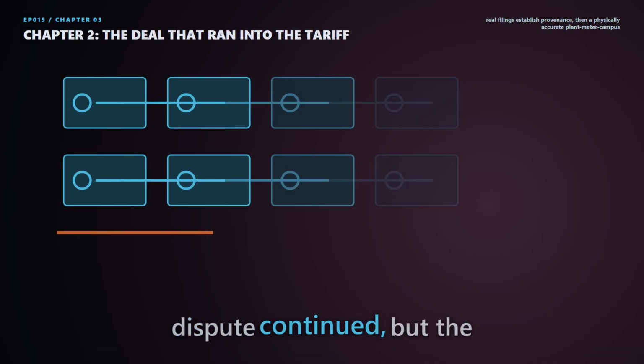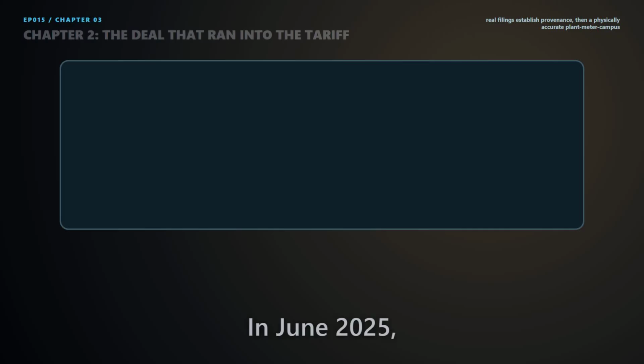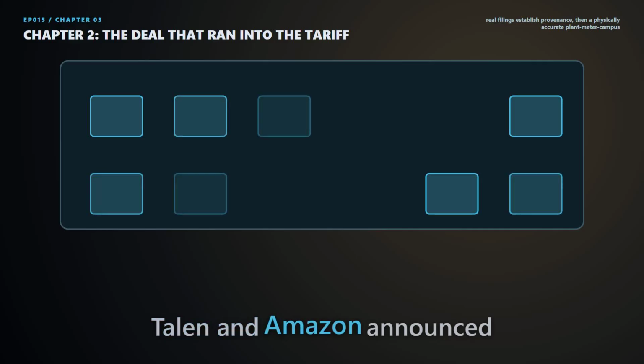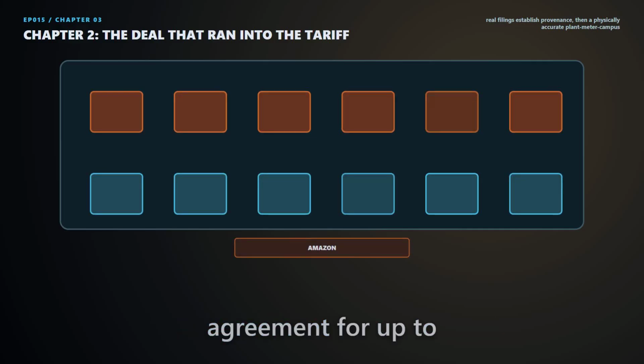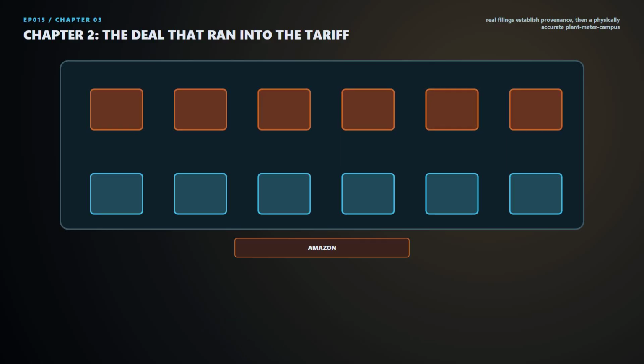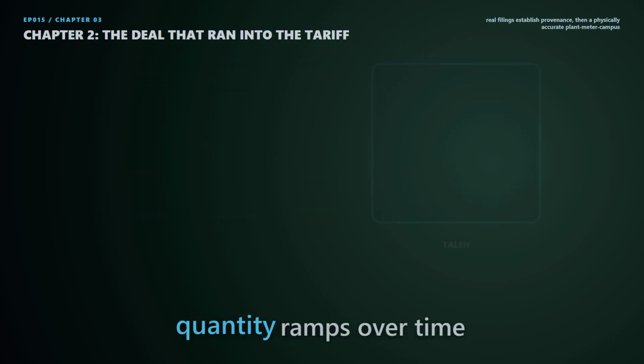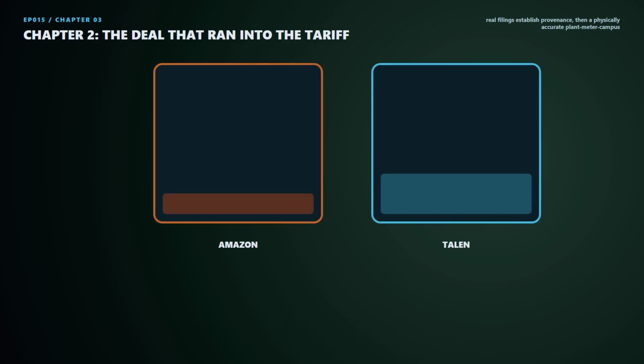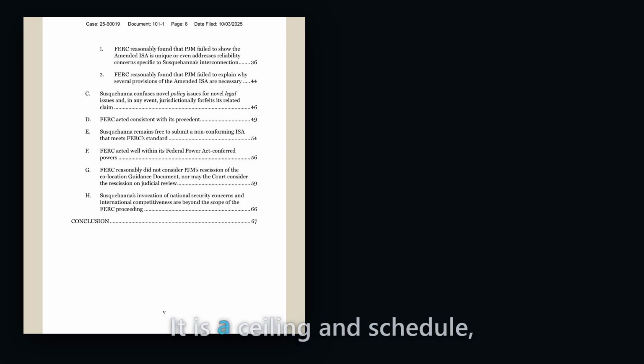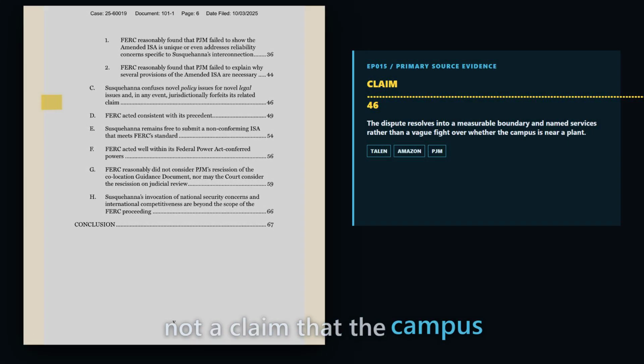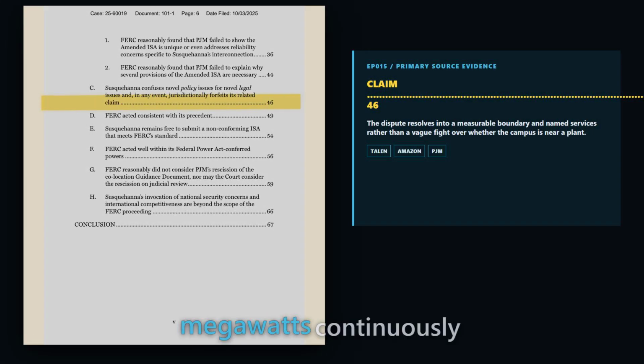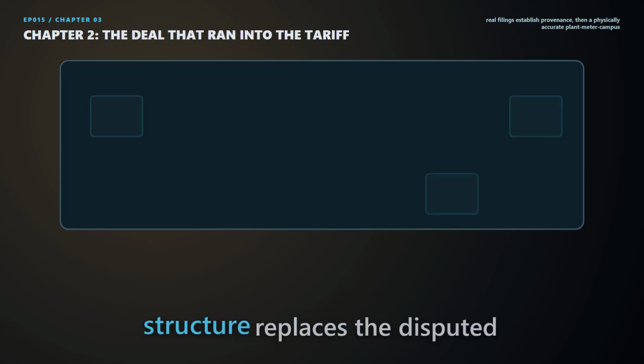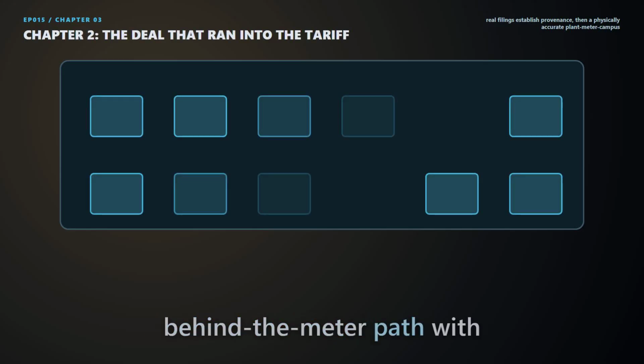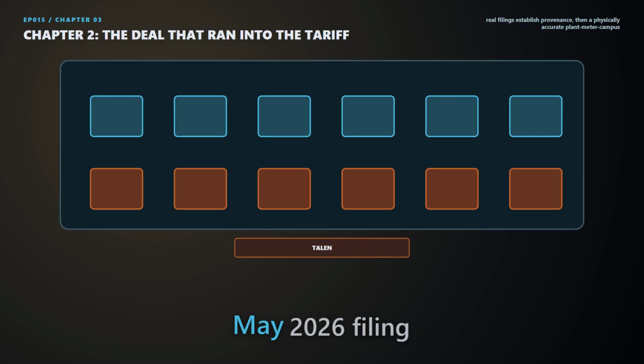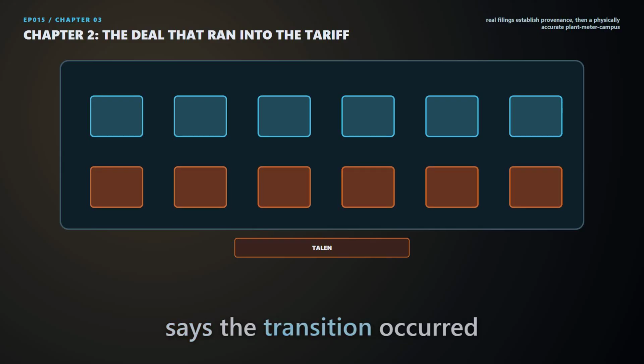The legal dispute continued, but the commercial arrangement changed. In June 2025, Talen and Amazon announced a revised power purchase agreement for up to 1,920 megawatts through 2042. The quantity ramps over time and is expected to reach the full level no later than 2032, with the possibility of accelerating. It is a ceiling and schedule, not a claim that the campus draws 1,920 megawatts continuously today. The revised structure replaces the disputed behind-the-meter path with front-of-the-meter service. Talen's May 2026 filing says the transition occurred in April.